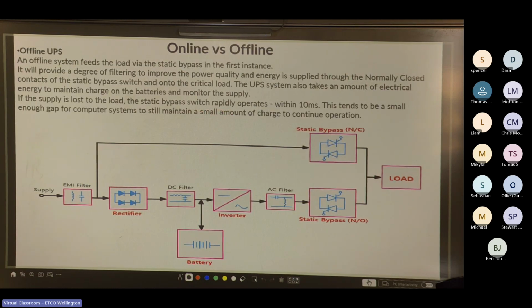So an offline UPS, the system feeds the load via the static bypass in the first instance. It will provide a degree of filtering to improve the power quality and energy through normally closed contacts of the static bypass switch and onto the critical load. The UPS system also takes an amount of electrical energy to maintain charge on the batteries and monitor the supply. If the supply is lost to the load, the static bypass switch rapidly operates, so usually within 10 milliseconds. There tends to be a small enough gap for computer systems to still maintain a small amount of charge to continue operating.